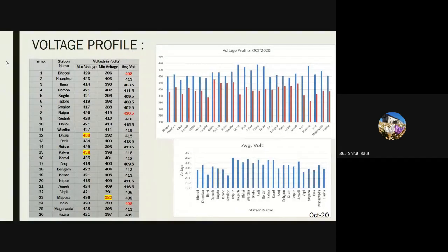Then Raigarh, so a representative from Chhattisgarh said the Raigarh substation is connected to Kotra pooling substation, which is connected to many IPP. IPP means independent power producer. So hence all IPP connected with Kotra substation need to absorb MVAR as per their capability curve. Also, JPL and TRN. JPL means Jindal Power Plant, and TRN is Thermal Energy Company in Chhattisgarh. They are connected with Tamnar, which is further connected to Kotra, and Kotra is already connected to Raigarh. So the voltage at Raigarh is high. For this reason Dhule and Raigarh got the highest voltages.